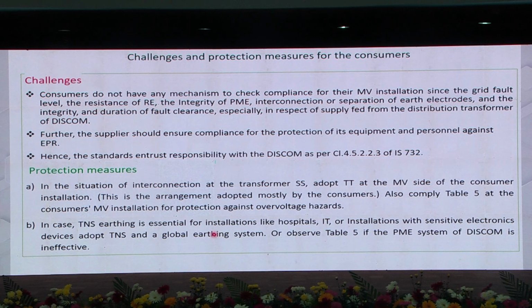I visited Hyderabad along with Mr. Gopal on a specific issue. We found, even in that location where the soil resistivity is more than 500 ohm meter, somewhat rocky soil, with the global earthing system, a Type B earth ring run around the building for lightning protection. So all the things getting interconnected, we measured an earth resistance of 0.1 ohm. If you have, for example, a 10 kA rating, then it's a case of 0.025. But you have your own HT breakers that can be tuned, so you can have enough fault current to get the system protected.